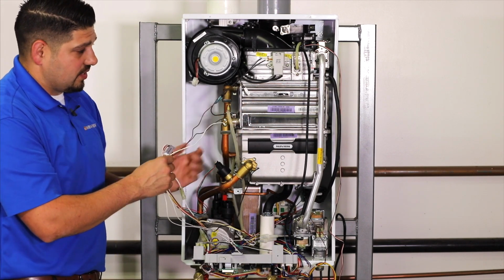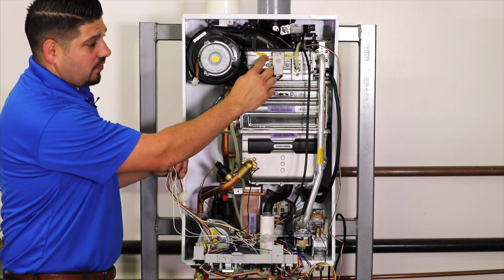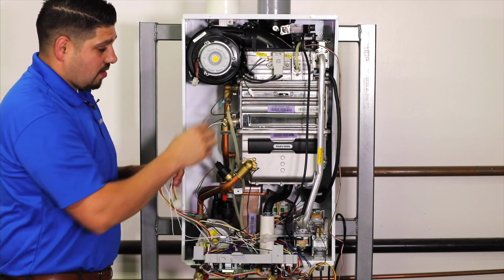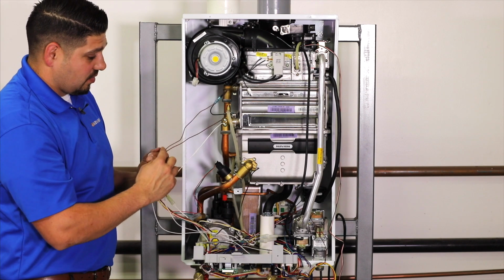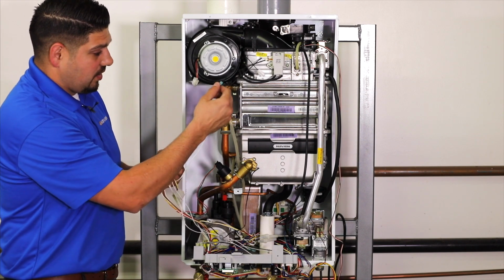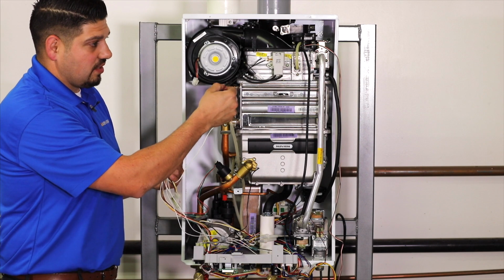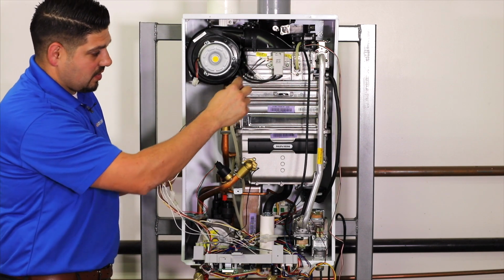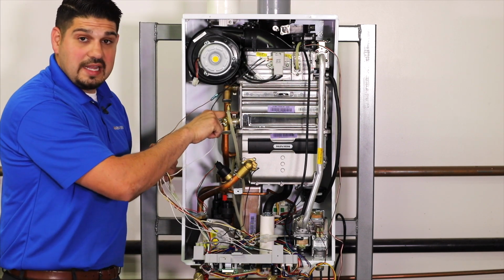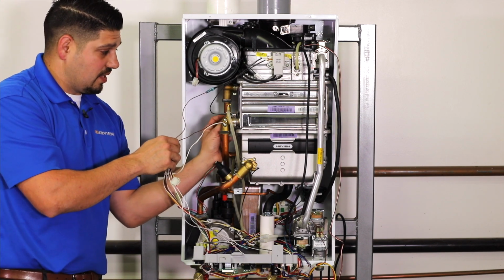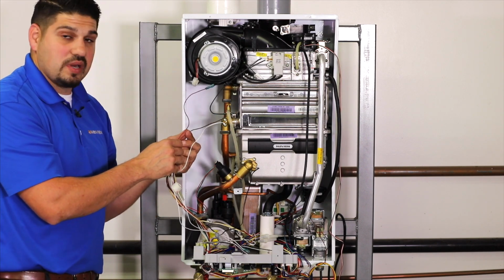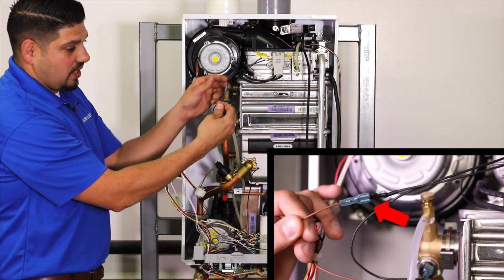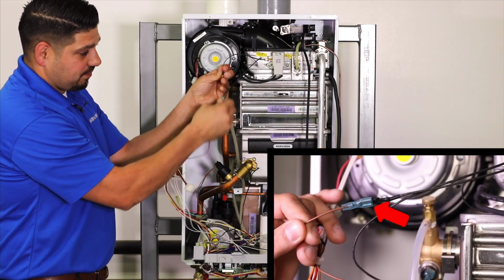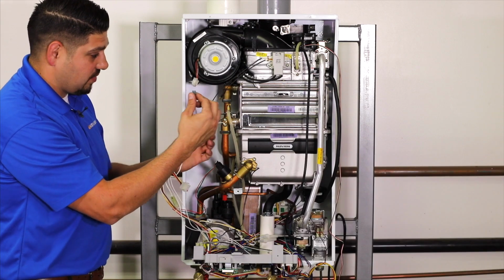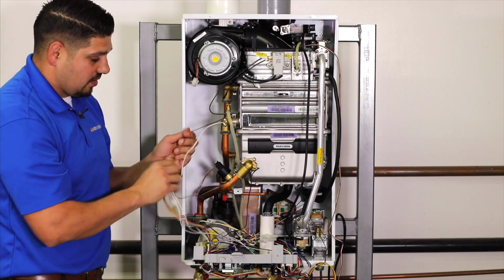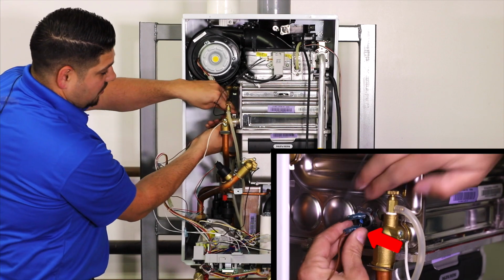Now, something to remember is this high limit and this thermal fuse on your burner here are wired in series. So the connection is going to go in through here, this brown wire, connected to one side of your thermal fuse, go around in a loop, come back out into your high limit that's located on your heat exchanger, and then go through that and back out to this brown wire. So this brown wire connects to this black wire, which is going to be a little confusing later on, so make sure you're well aware of that. And then the other end of the brown wire connects to one end of your heat exchanger.